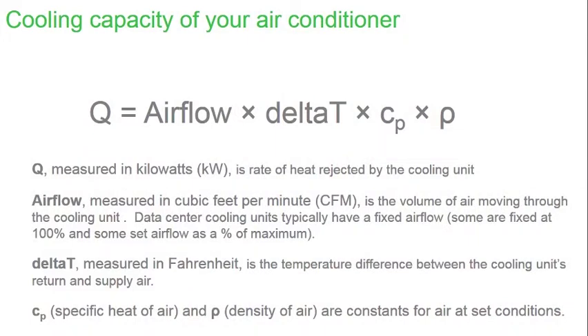It's not enough to know that there is this delta T thing — I want to get into the formula for how to reject heat from a cooling unit. I don't mean this to be complicated; we're trying to simplify these things. When you look at the formula and we simplify it, you're going to realize what I'm trying to do. Here you can see that Q is measured in kilowatts — this is the formula we use to calculate how much heat is rejected from the cooling unit, and that heat will be the heat from your IT equipment.